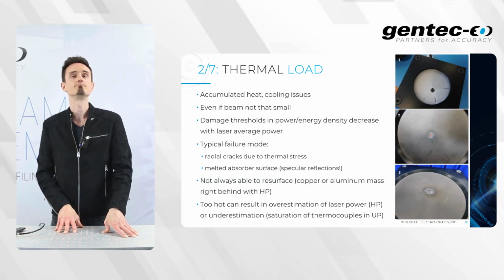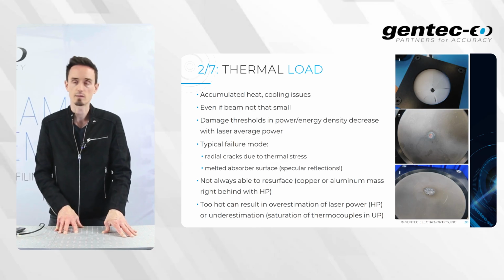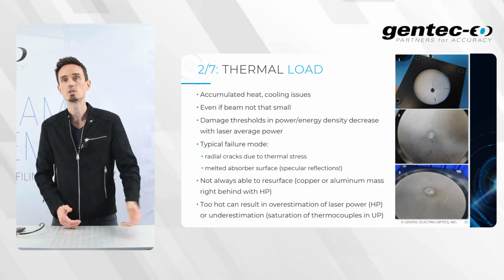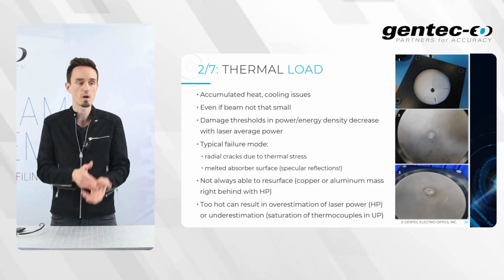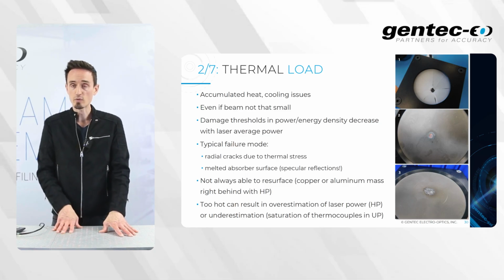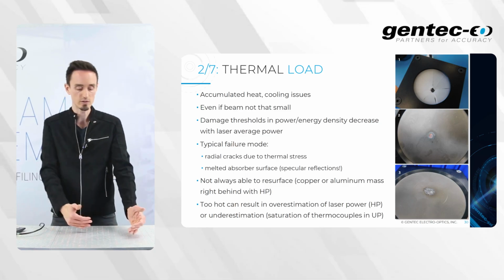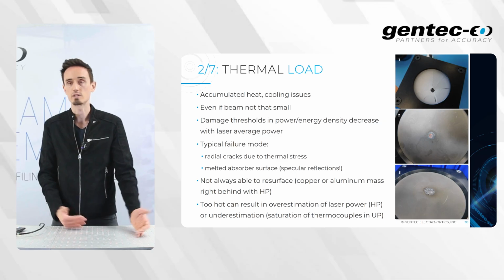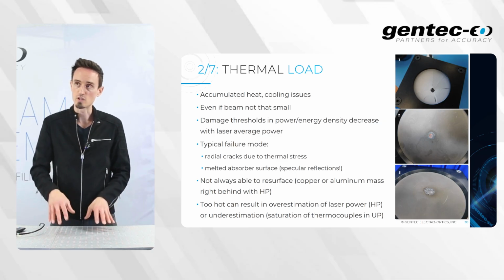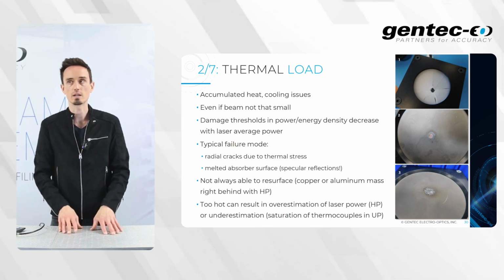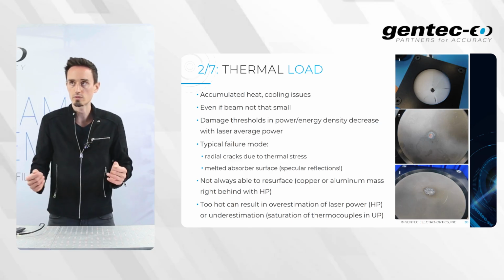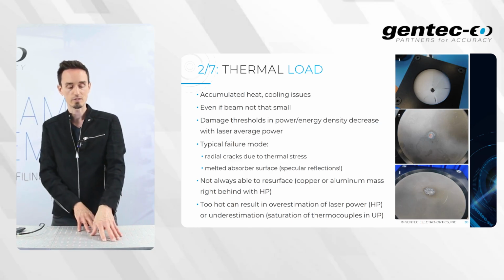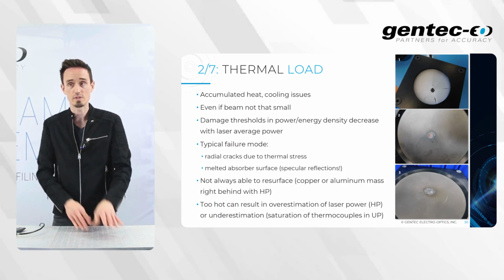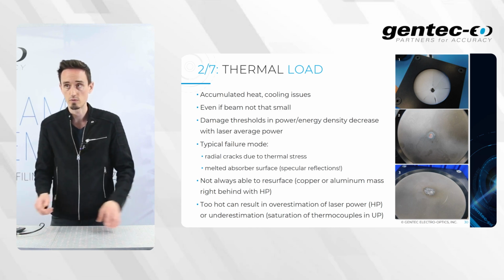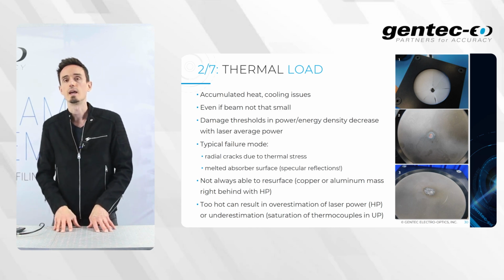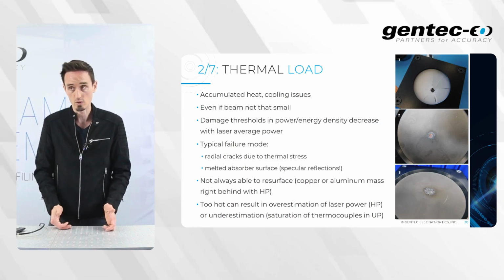Okay, the second one, thermal load. Yeah, that's the realm of accumulated heat and some cooling issues. Even if the beam is not that small sometimes, because the damage thresholds in power and energy density decrease with the laser average power and the ambient temperature. The typical failure mode here looks like some radial cracks due to thermal stress, as you can see on picture 1. Some melted absorber surfaces, for example, resulting in bad specular reflections, if you look at pictures 2 and 3, and we're not always able to resurface those detectors.